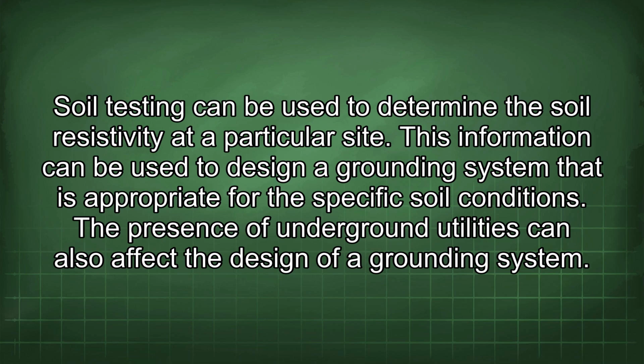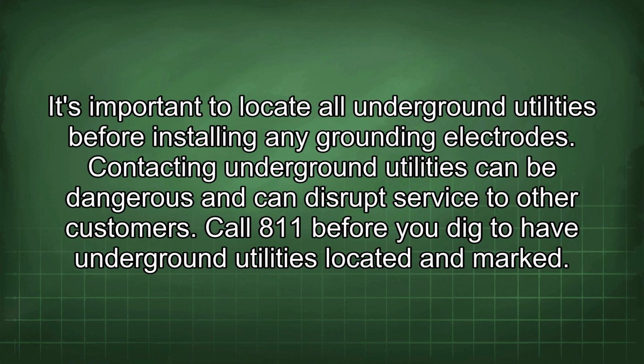The presence of underground utilities can also affect the design of a grounding system. It's important to locate all underground utilities before installing any grounding electrodes. Contacting underground utilities can be dangerous and can disrupt service to other customers. Call 811 before you dig to have underground utilities located and marked.